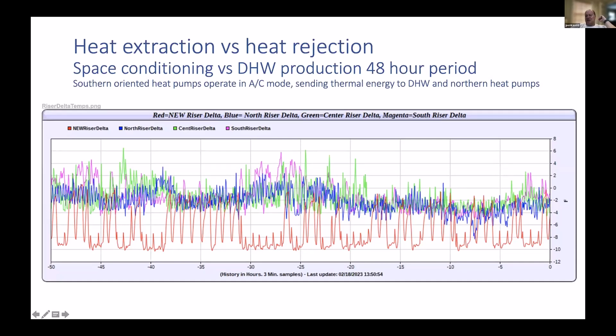So here they're exchanging only energy between different portions of the building. But look how the loop field is reacting to the input and output in that way. Now, the magenta line here is the southern portion, and this is the warmest one. So this is where we have the most heat rejection coming into the loop field in February. Everything above zero is rejecting heat. Everything below zero is extracting heat out of the loop field.